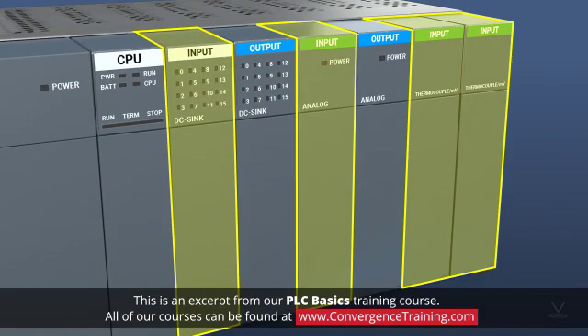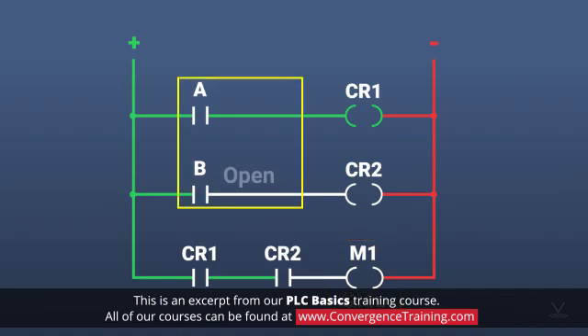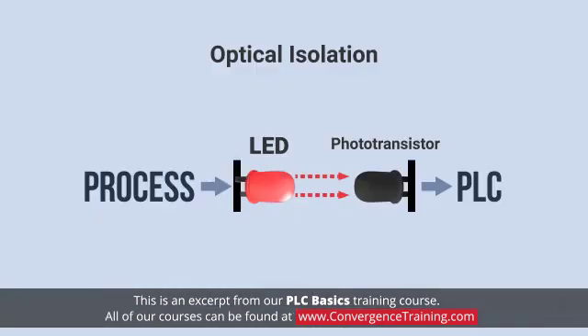PLC input modules accept electrical inputs from process components in the field and convert that information into a computer-compatible data file. Historically, PLCs have dealt with logical binary information such as whether something is running or not running, whether a switch or relay is open or closed. Digital input cards usually apply a technique such as optical isolation to prevent any line level voltages coming into the module from damaging low voltage circuitry in the module.